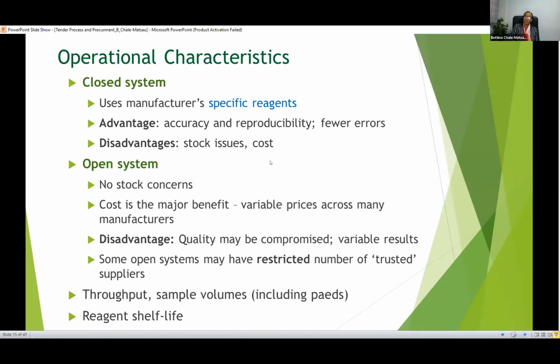The open system, on the other hand, is where the manufacturer says you can use any third party. The advantage here, which is actually huge, is that because you can use other reagents, you don't really have stock issues. However, the disadvantage is that quality may be compromised, because if you're using multiple suppliers, you could have situations...